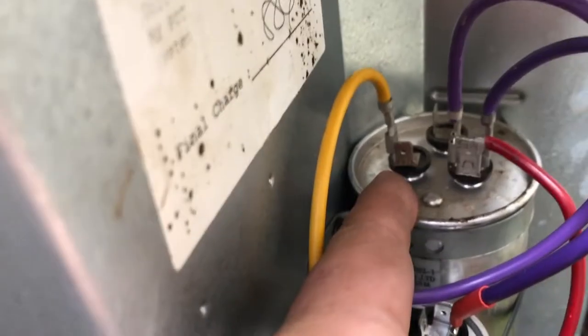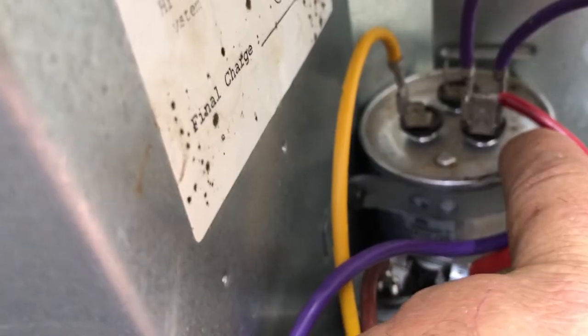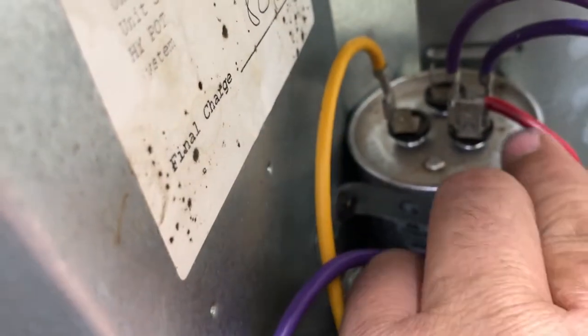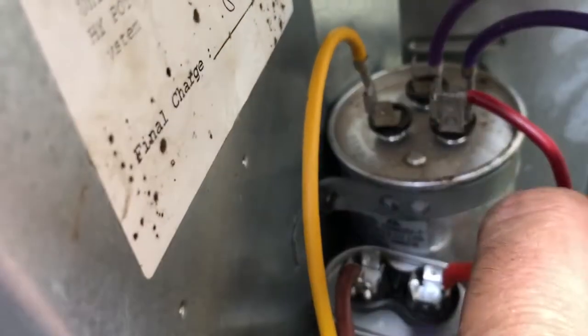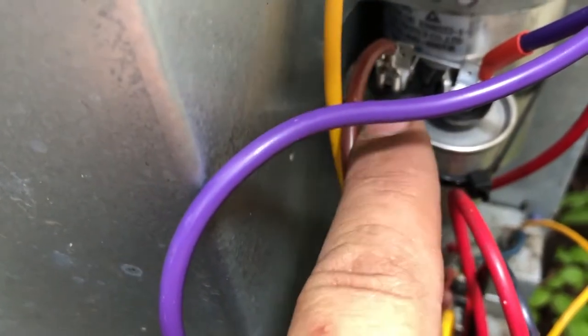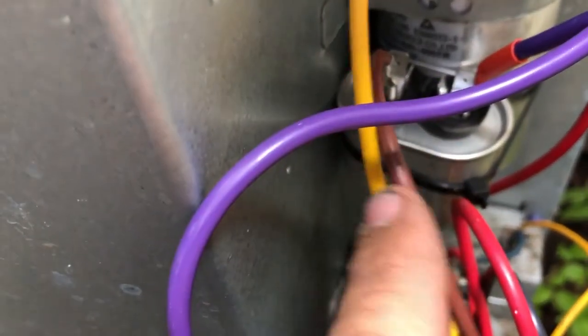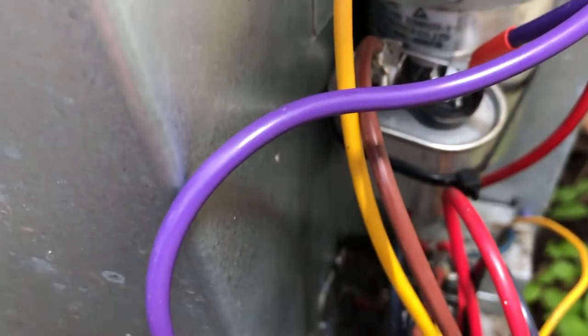You'll have a wire that connects here called HERM - that's the one that feeds your compressor. This red wire coming up is going to be your hot, they call that common, it'll be marked C - that's your voltage in - and that will usually have one wire going to the fan as well. Then there'll be another wire that goes to the fan, which is this brown wire. Once it's running, this purple wire powers it, and the brown wire starts it. So there are three wires coming from the fan.